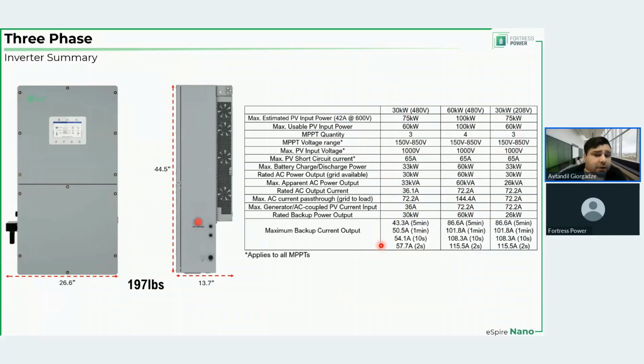We also obviously have AC output rated at 26 kilowatts for the 208 volt 30 kilowatt unit, 30 kilowatts for the 480 volt 30 kilowatt unit, and 60 kilowatts for the 480 volt 60 kilowatt unit. But for brief periods of time, it can output even greater current. So compared to a nominal of 36.1, for example, the 30 kilowatt 480 volt inverter can output 43.3 amps for 5 minutes, 50.5 for a minute, 54.1 for 10 seconds, and 57.7 for 2 seconds, and even higher numbers for inrush or surge. And you can see the numbers for yourself.